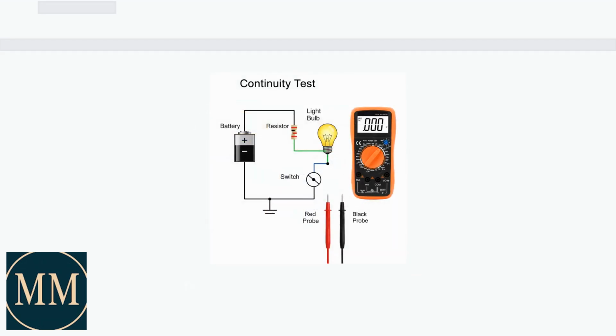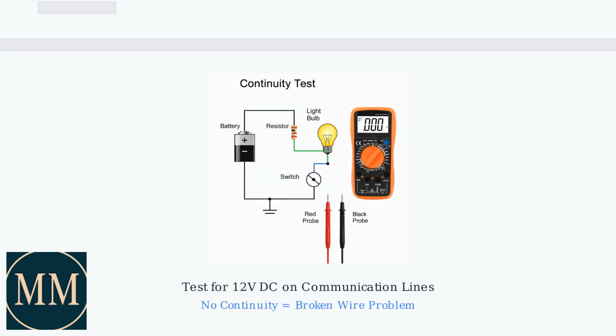For communication lines, specifically test for 12-volt DC signals. Switch the multimeter to DC voltage mode and check the lines for the expected 12 volts. A lack of continuity or missing 12-volt signal indicates broken or shorted wires that are disrupting communication. This problem needs to be addressed by repairing or replacing the affected wiring.